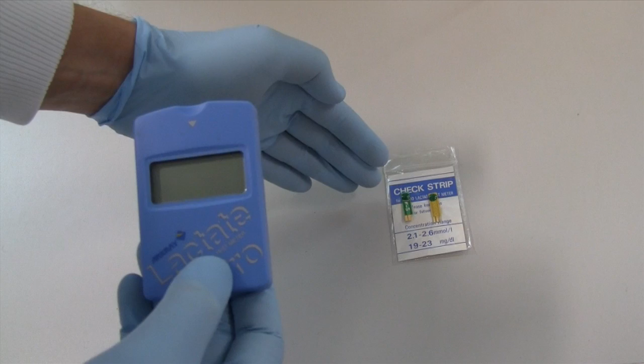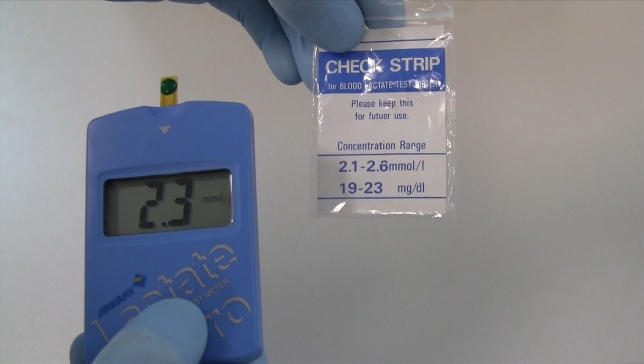calibration strip, and this has a lactate concentration of a known amount, and it's 2.3 millimoles. And for this particular check strip, the reference should be between 2.1 and 2.6. So we know this piece of kit is working absolutely fine. Once you've done this, you're then free to measure your blood sample.